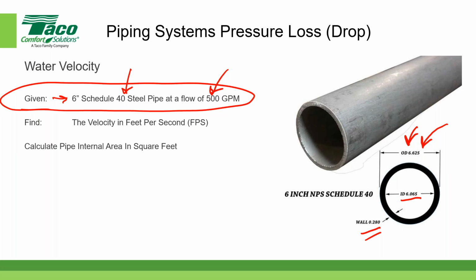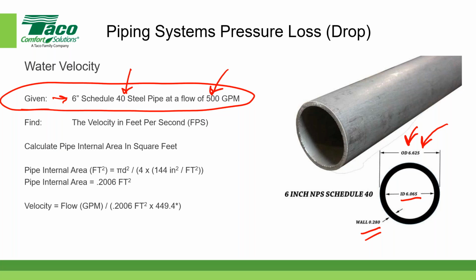We're going to calculate the pipe internal area in square feet. And the way we're going to do that is simply use a very simple formula that says the area is equal to pi d squared divided by 4. And so if you want to convert square inches into square feet, we're also going to divide by 144. And in our case, our internal area is 0.2006 square feet.